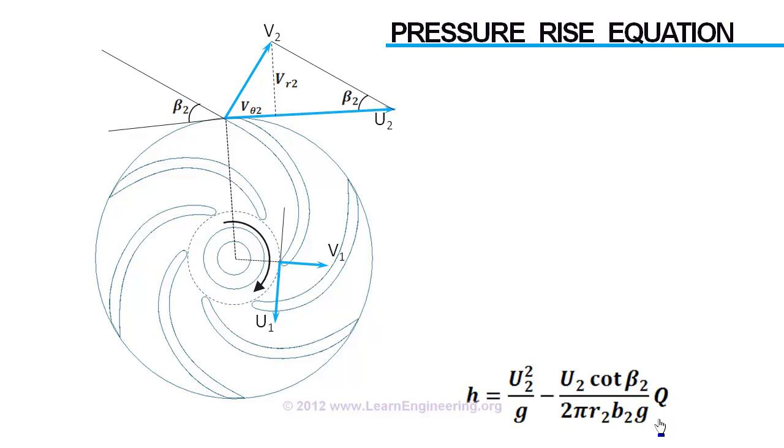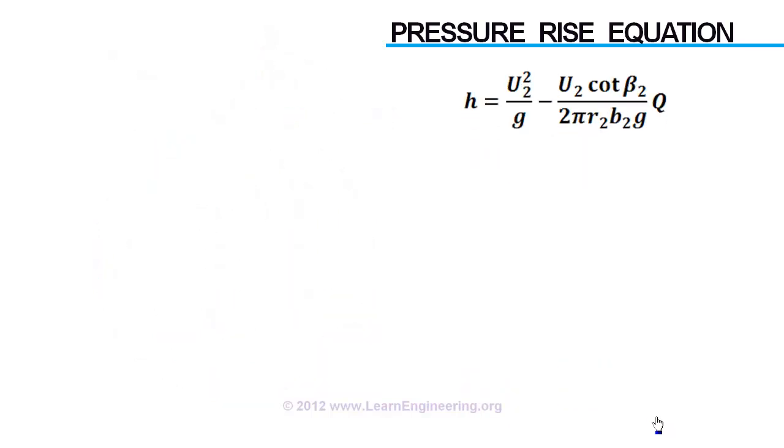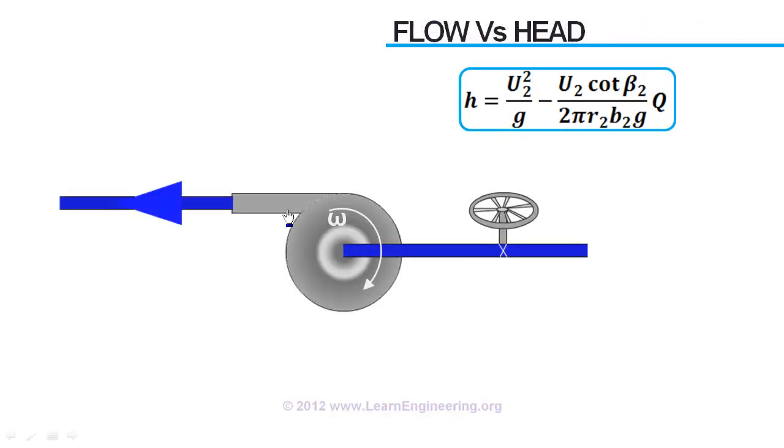Using this we can predict what's the head rise as we change the flow rate for a particular pump geometry and a particular impeller angular velocity. Most important parameter in this equation is blade outlet angle, beta. There can be three different pump characteristics depending upon value of this angle.